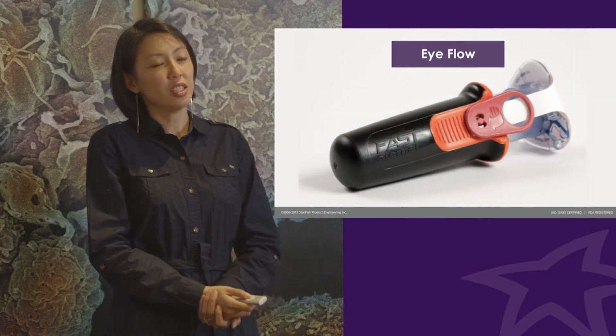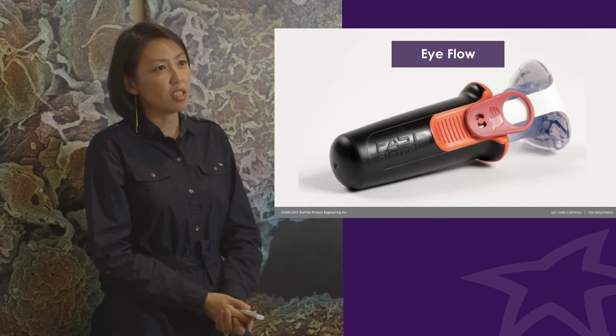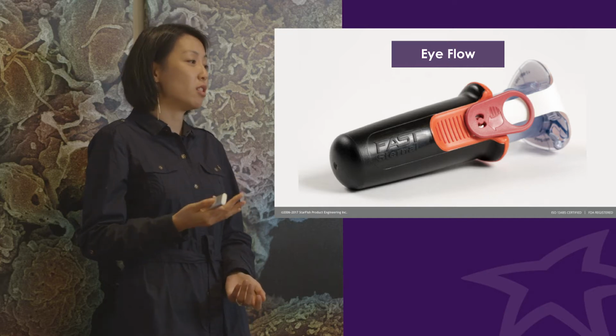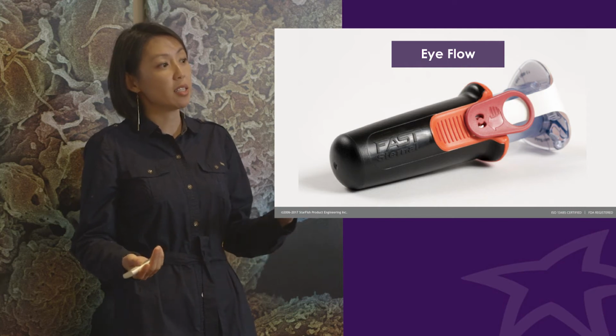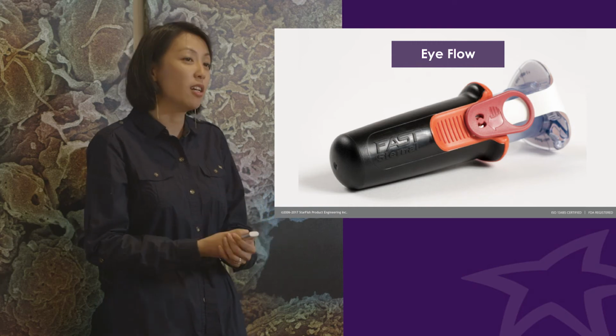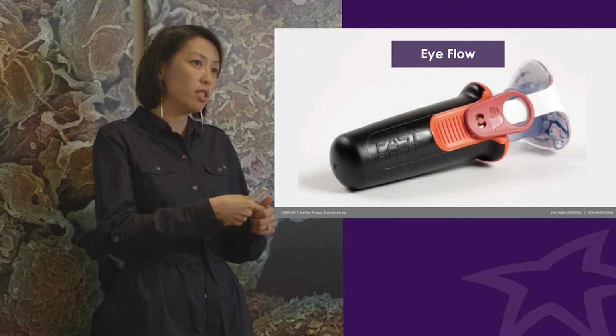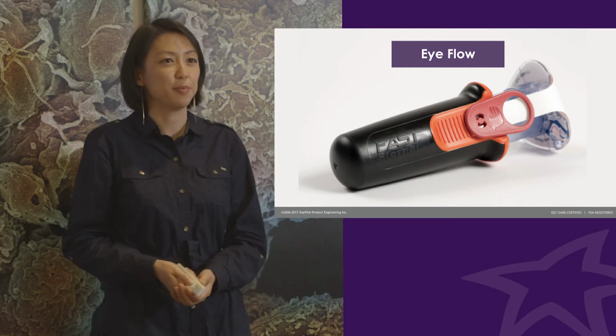This is a sternal intraosseous device that we designed for military use. Our client asked us to make this whole thing just black because all of their devices were black, but we convinced the client that that wasn't the right direction because in a combat situation, medics don't have time to figure out which way to hold the device and how to interact with it, right? So we highlighted the pull tab with this bold red because red calls your attention. And then once they pull the tab off, they can see the orange thumb placement.